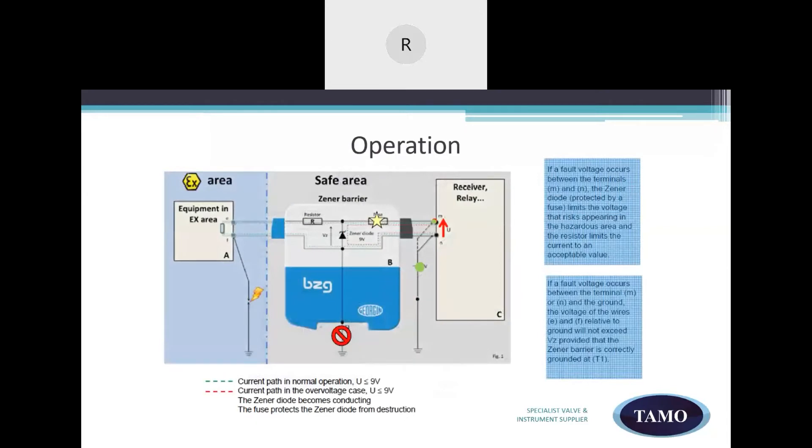The operation. The Zener barrier interfacing mode differs from others as there's no galvanic isolation. Cables that pass through the hazardous area share common features with those of the safe area. This implies equipotential ground mounting of the barrier. It is important to ensure the equipotential ground between the interface product, the barrier, and the PLC to avoid the occurrence of a potentially harmful ground current.